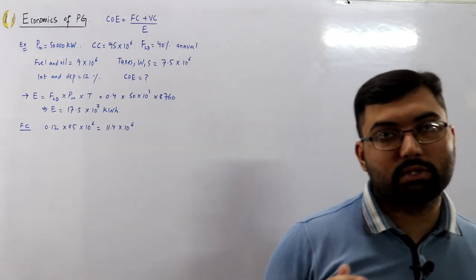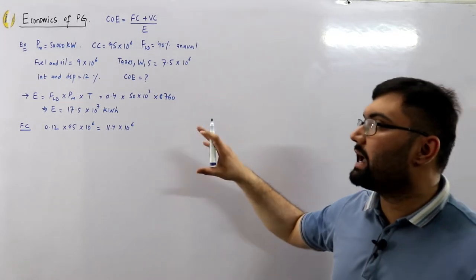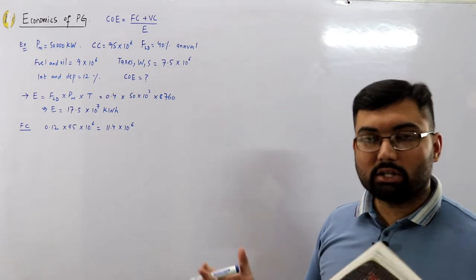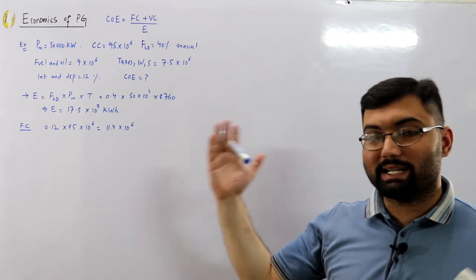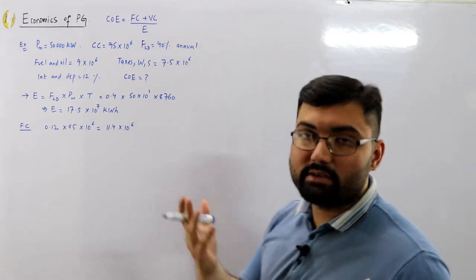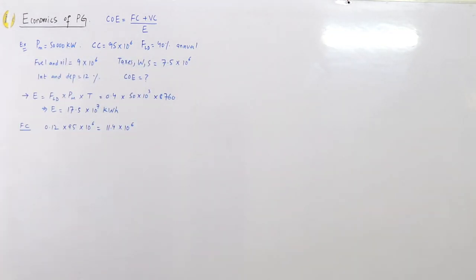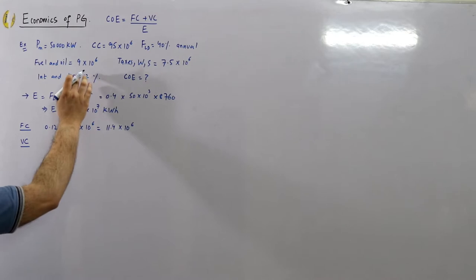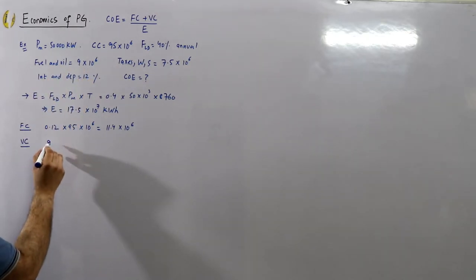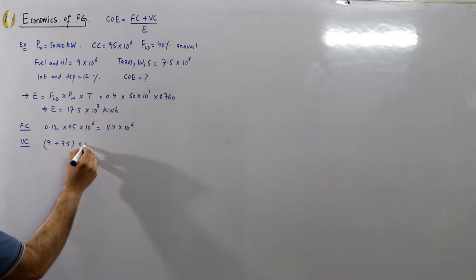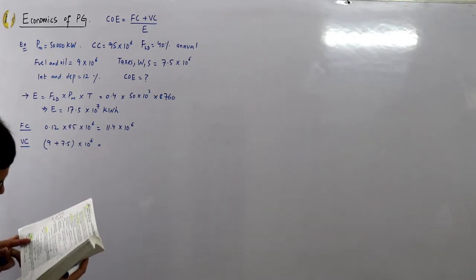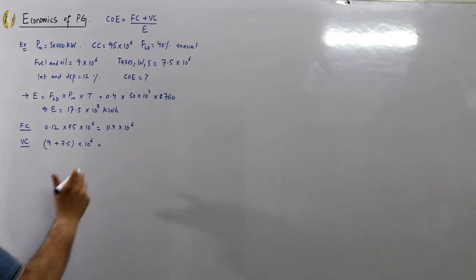You may ask why we don't take the full capital cost. We are dealing with annual calculations, and the capital cost is spread over the entire lifespan of the equipment — 40 to 70 years. The variable or running cost includes fuel (9 million) and taxes, wages and salaries (7.5 million): 9 + 7.5 = 16.5 × 10⁶ rupees.